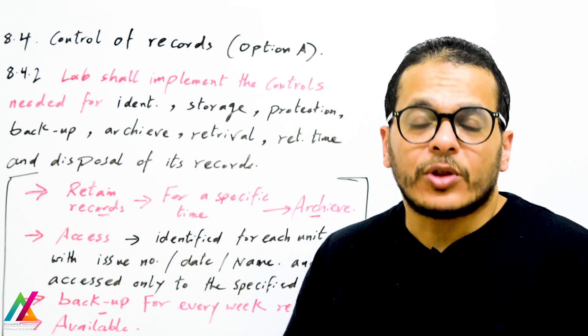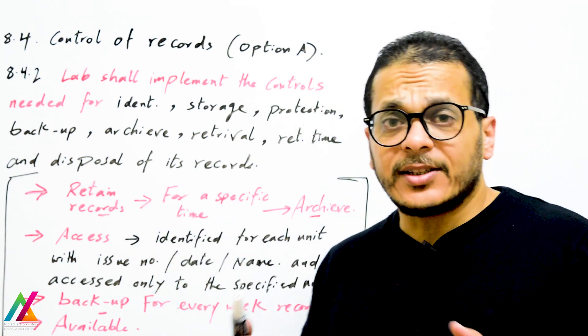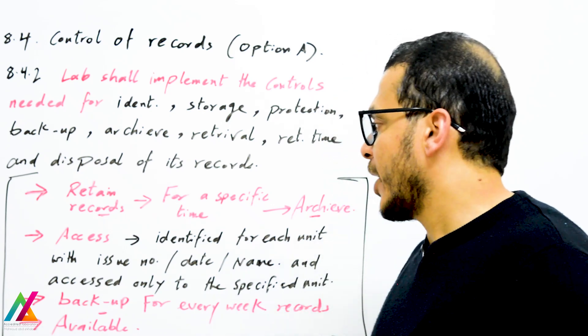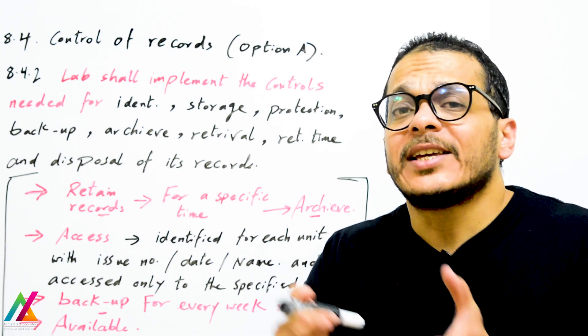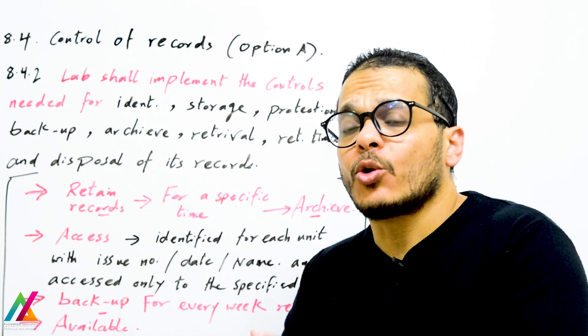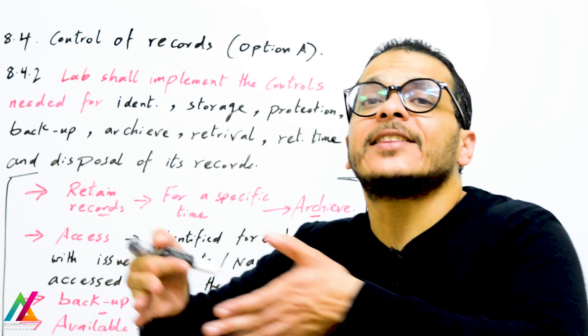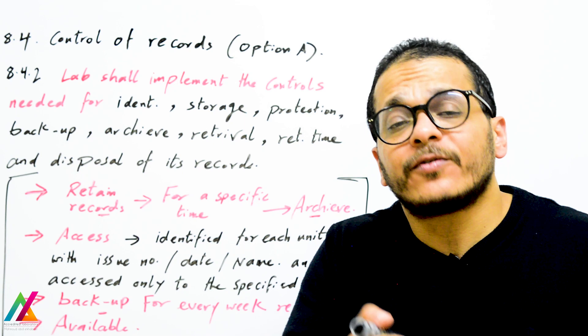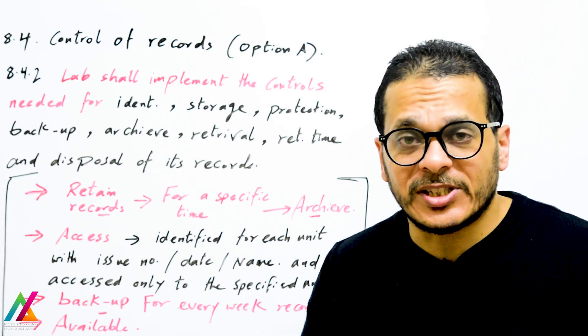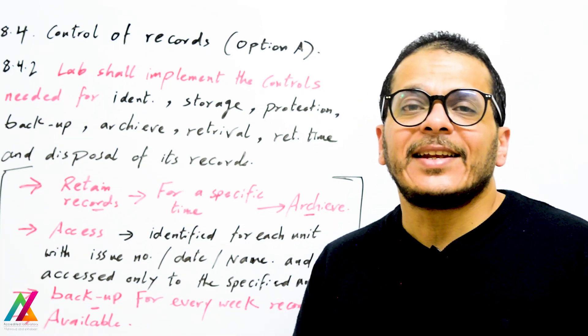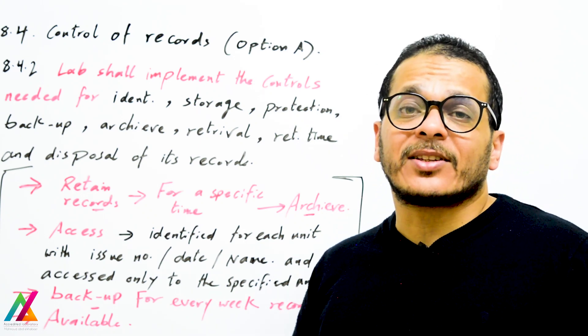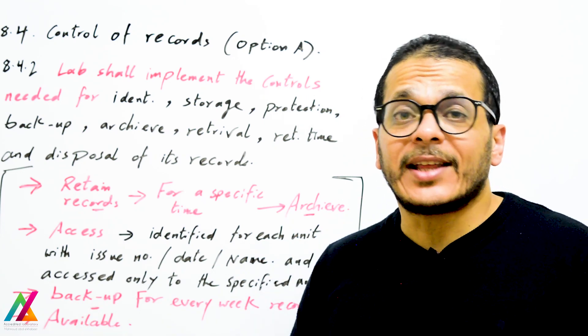The lab shall implement controls for identification, protection, storage, backup, archiving, retrieval, retention time, and disposal of its records. Although not mandatory, it is highly recommended to have a specific procedure covering all these points. Identification means records shall have a specific name, issue number, and issue date. Access to records should be controlled for only the specified unit — hard copy records kept in a dedicated file, and digital records in a specific controlled folder.